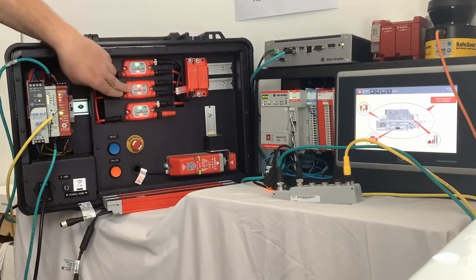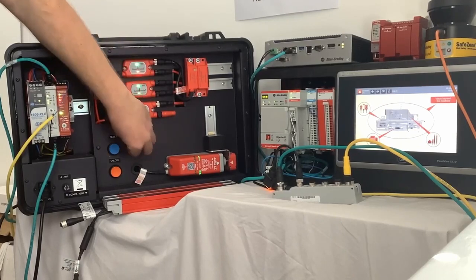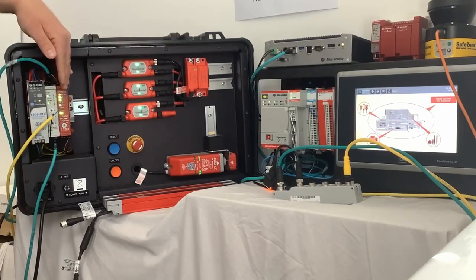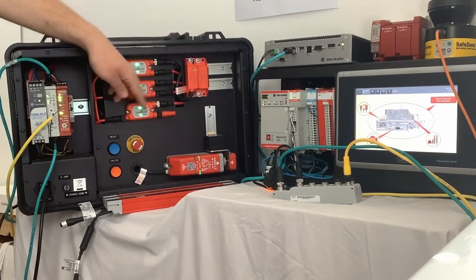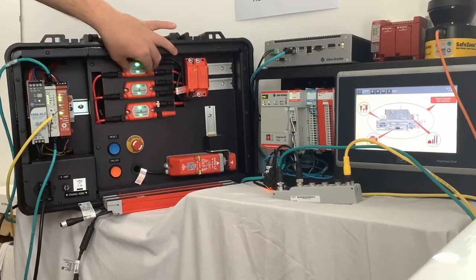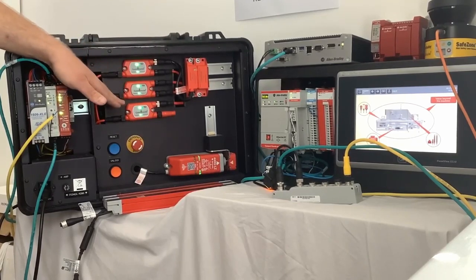Then on here, we've got an E-stop, which goes to the middle tap. So press that, you see that's gone red. This is obviously a dry contact switch. So the tap is slightly different. It's called EMSS. So basically all it's doing is, like your safety relay, it's putting test pulses out on the legs for that device. Whereas this one obviously doesn't need to because it's an OSSD device. So you just buy the tap for the device.